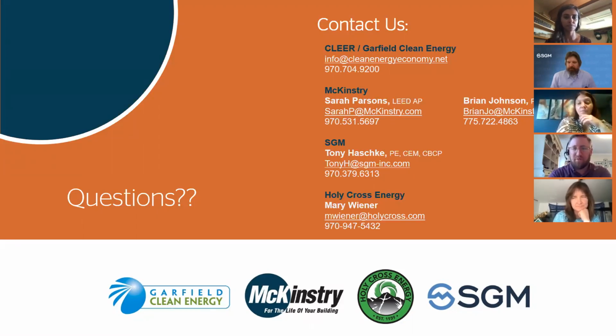I'm curious why it was changed to not being operable. There may be some liability issues or something that you have to consider with that, but from an occupant comfort and a coronavirus safety standpoint, yeah, I think operable windows are great. Definitely want to consider any contaminant sources. Look at, do you have a restroom exhaust fan that's within 10 feet, or is actually below windows, side-walling or anything like that. You want to make sure you aren't bringing in contaminants by making them operable. But good point.